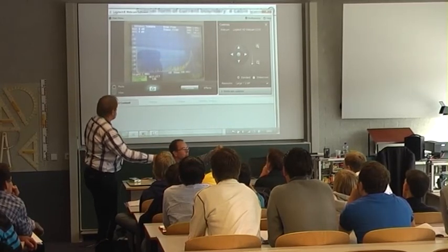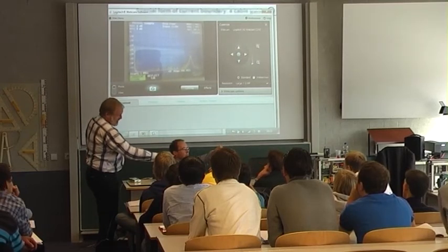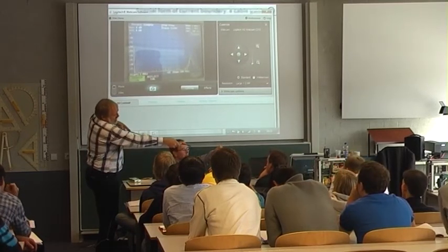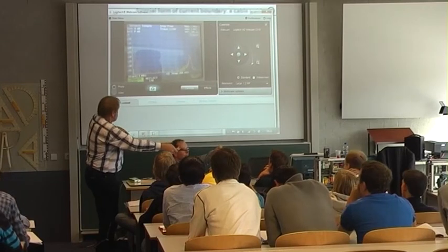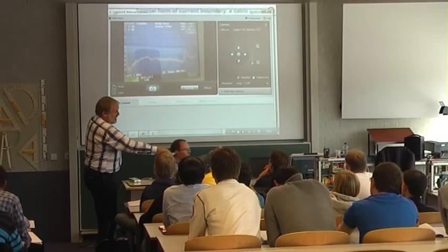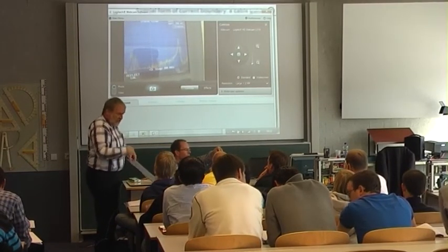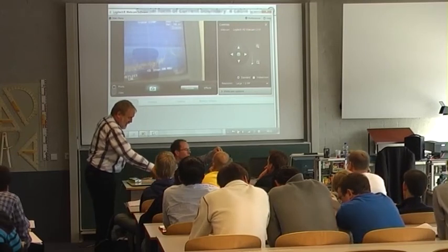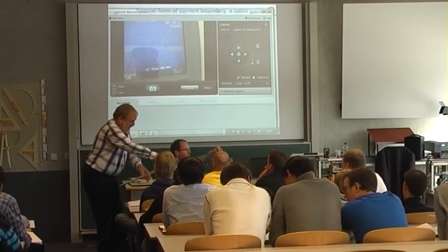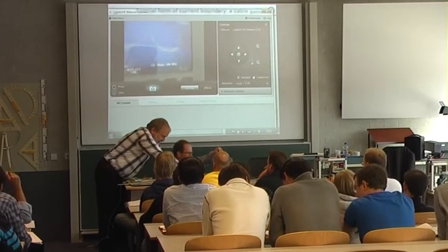It only works if you have good contact. There's still a little interference here, but it's low, and there's a little opening here, and you can see it in the high frequencies. No contact, everything is bad. So yes, you need an alternative connection, which is a good low impedance contact. Okay, so this is the ideal use of a metal plate.